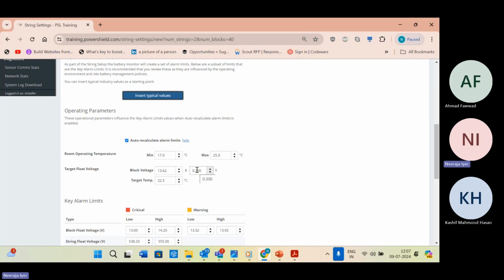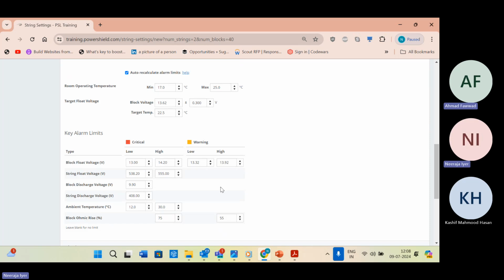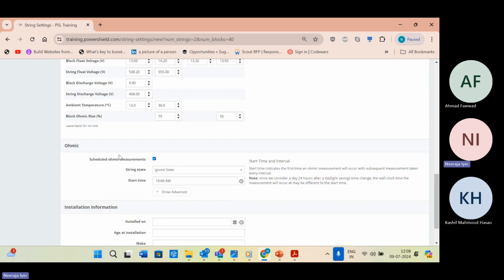Please note these alarm limits are user editable. It is just for the start of the configuration until the system settles down. Then we go ahead with the alarm limits that we have arrived at over a period of time. That is the advantage of automatic 24/7 battery monitoring systems. Based on our experience, this itself will set alarm limit thresholds. Then you have the ohmic value. Please make sure you check this box of ohmic measurement, because our system has functionality to provide you automatic ohmic measurements.